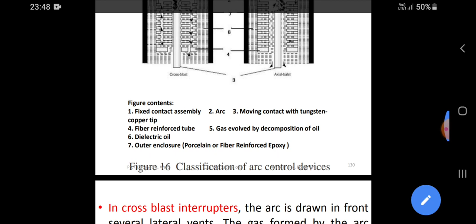In the cross blast interrupter, the arc is drawn in front of several lateral vents. The gas formed by the arc causes high pressure inside the arc control device. The arc is forced into the lateral vents in the pot, which increases the length of the arc and shortens the interruption time. The axial blast interrupters use a similar principle as the cross blast interrupters. However, the axial design has better dispersion of the gas from the interrupters. The figure shows the circuit breaker.